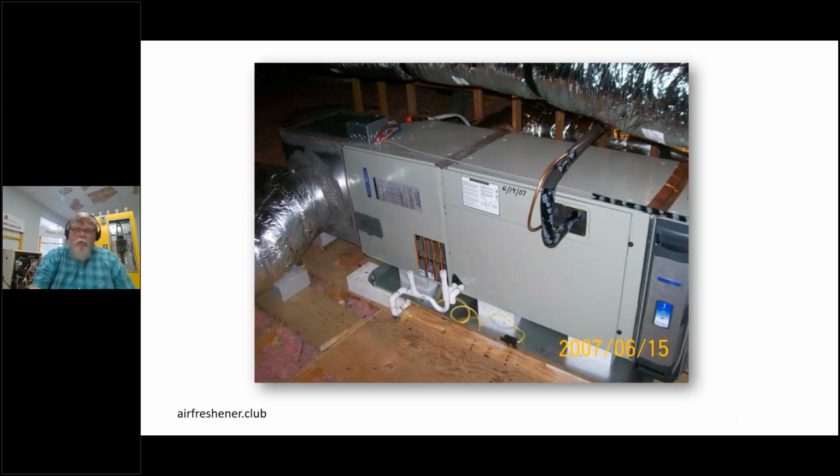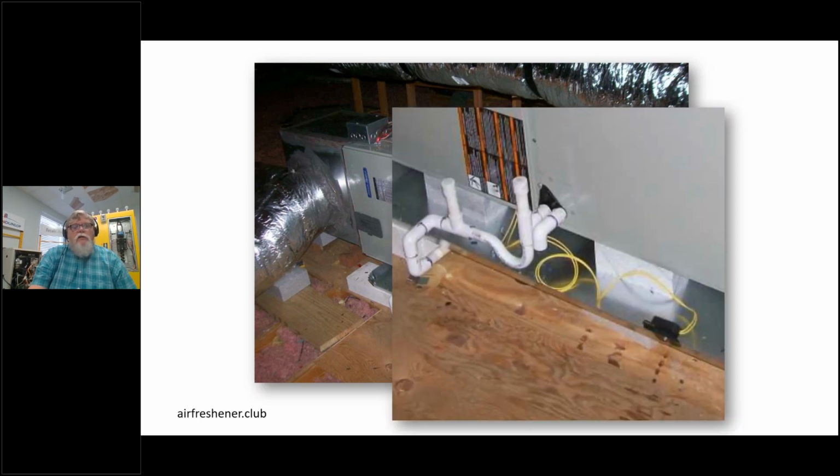I think I'm about ready to wrap up here, but if you look at this unit, they did a pretty good job. They got the T's, got a little riser pipe in there with probably a press on cap. They got a float switch inside the pan, but they put an elbow turned down into the pan so that if this unit actually fills up with water, something happens, the trap gets blocked or whatever, it fills up with water, it runs into that pan.